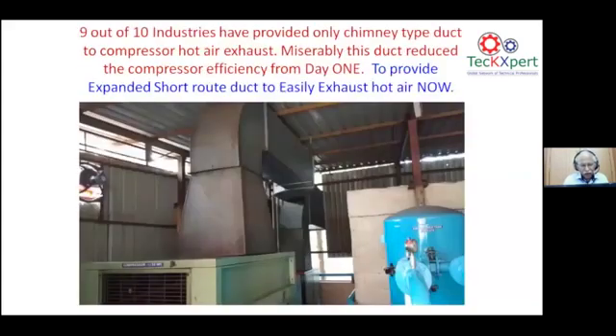Next comes the hot air exhaust from the compressor, which is kept as a chute or a chimney. This chimney type of exhaust is a heavy loss to the compressor house, and the compressor house temperature goes up by 5 to 10 degrees. Also, let us say the open size at the top is 2 feet by 2 feet. Minimum it should be 50% more, say 3 feet by 3 feet. It should be expanded, and the length of the expanded duct should be short, so it exhausts the heat easily and effortlessly. Then only the compressor house will be at ambient temperature and the compressor also will be healthy.